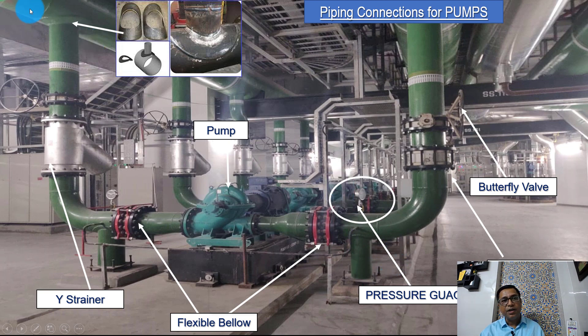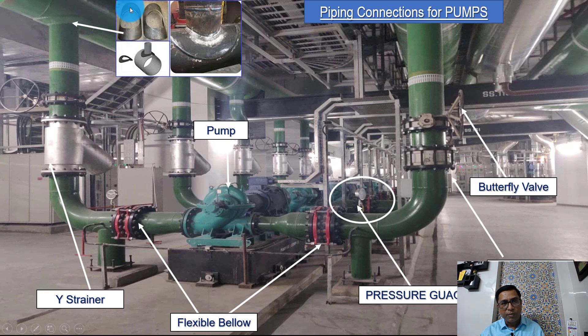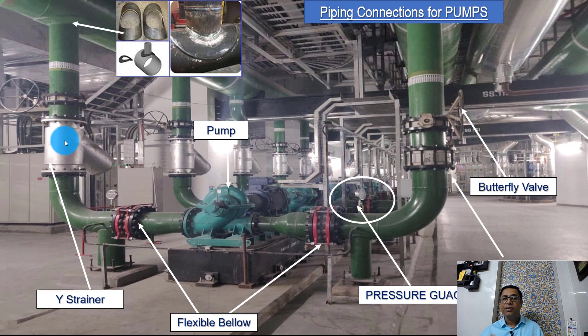Now, just to give you a brief: when we take the tap off from this header, that area gets weakened. And that is why you can see there is a reinforcement pad which is welded separately, coming out of this mother pipe. We have this reinforcement pad here which gets welded like this — you can see this picture properly. Similar thing is replicated here, so this is a strong joint, there is no weakness here, and we have a system running for a long, long time without any issues. This is the actual practical installation which I thought I should bring to you.